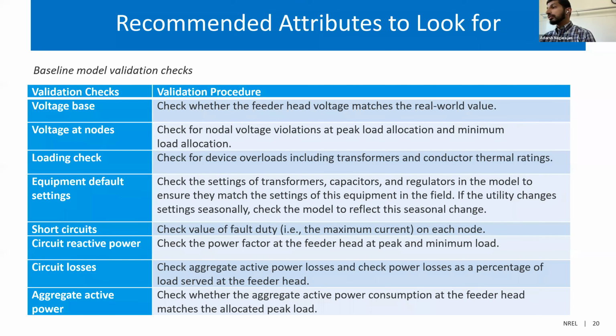Look for device overloads, including transformers and conductor thermal ratings. For example, you can look at transformer loading. For whatever reason, you may see many transformers 150% loaded, which is not the scenario you were expecting. That can be a good checkpoint to go back and perform root cause analysis.